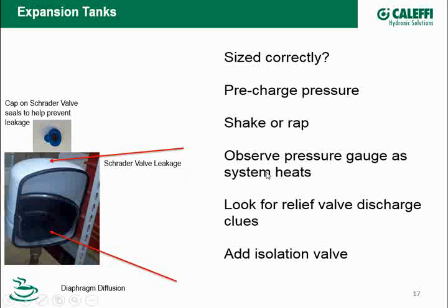Another way to see if your tank's been waterlogged is fire the boiler up and see what the pressure gauge does. If the pressure gauge starts jumping up quickly as soon as the fire comes on and the expansion of the fluid goes up, a good chance that you've either got a bad tank or you've got one where the air charge has been lost in it. And the other thing to look for, if you see that the relief valve's been popping off, you see a little stain on the floor with the pressure relief valve on the boiler, that's another indication that you've got a tank that's, number one, either waterlogged or it's undersized, or it's lost some of its air pressure charge and you don't have enough expansion capacity in it.